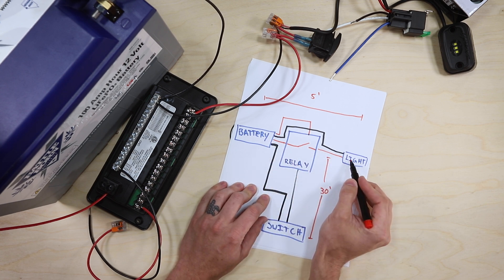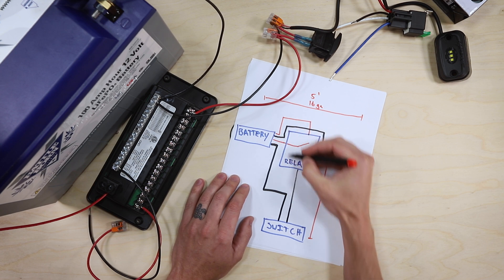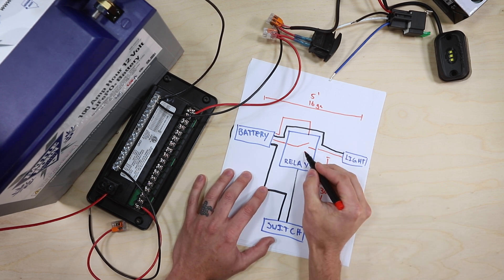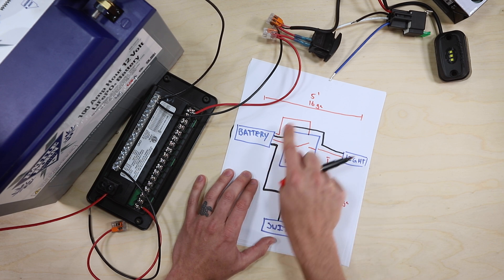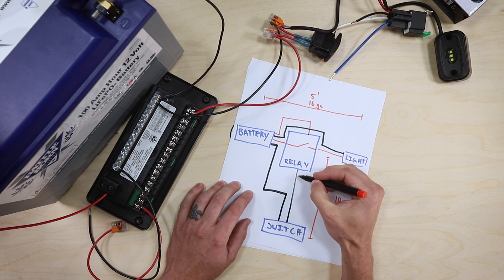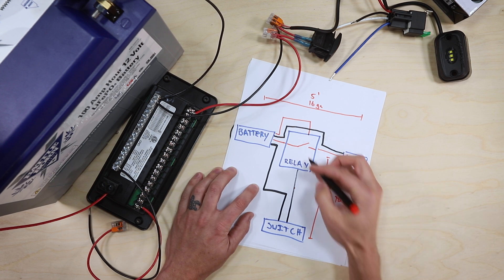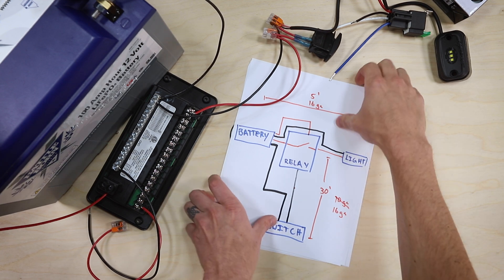If it's only five feet from there to there, we might be able to use 16 gauge wire for this particular light. But if we had to go 60 feet — 30 feet one way, 30 feet the other — we may have to start using 10 gauge wire to satisfy our voltage drop requirements. By using a relay in this location, it may not always mean less wire, but more importantly it means we can probably use smaller gauge wire on all of these circuits. This circuit that controls the relay is carrying just a few hundred milliamps — like 200 milliamps at the high side — so it's not enough amps to need big gauge wire. So even over a long distance, this can also be 16 gauge. Now let's show how this is actually wired.